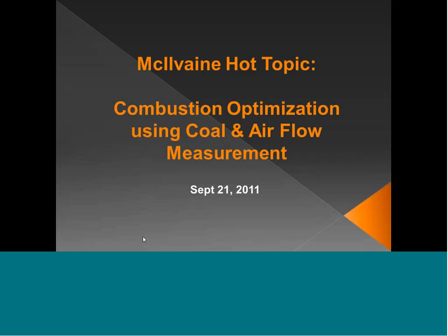Thank you, John. Guys, we're also looking at really high velocities. We've got huge burners, and we're looking at a little less than 10,000 feet per minute, so 150-some feet per second. There's no question that the higher your velocity, the faster you're going to erode anything, and it's exponential. Because we're on units that have converted from eastern coal to PRB coal in small diameter pipes, we have seen higher velocities in some cases, and it's a concern. The product hasn't been installed that many years, so we maybe only have 4 or 5 years of service now, but I wouldn't expect to get 10 years of service out of sensors if we've got high silica, alumina, for instance, and a high velocity. There's no question it is a concern, and it's something that should be looked at.